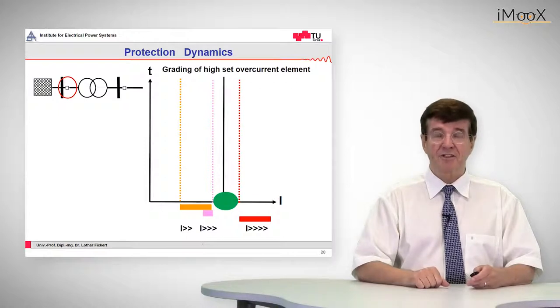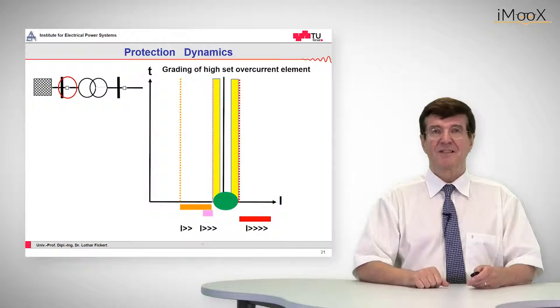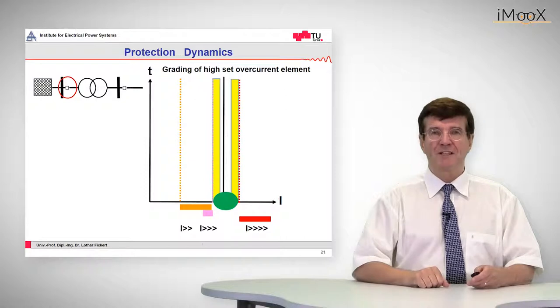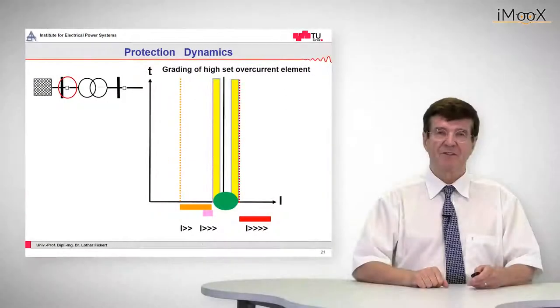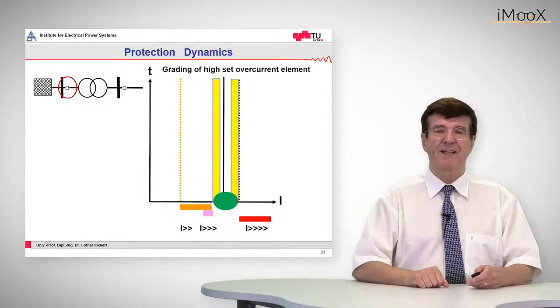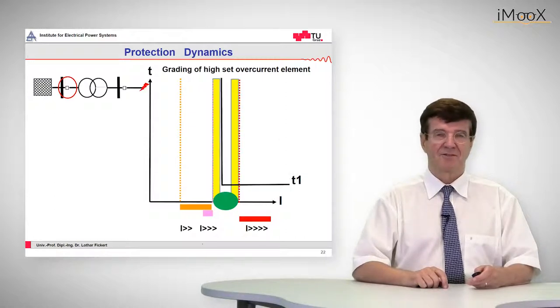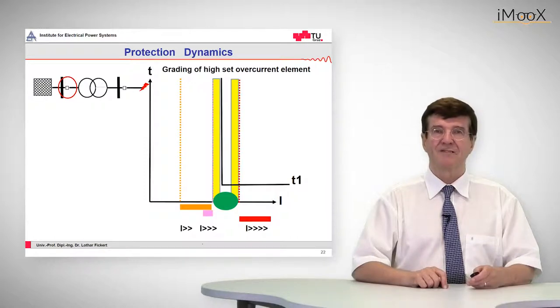In any case, the pickup value must not infringe with the safety margins. On the high set side, it must always pick up for a fault current, so the pickup value must be below that. On the other hand, it must not infringe with any fault on the low voltage side, so it must be above the highest low voltage side current. The tripping time is T1, because we must not wait for anything — tripping can be carried out immediately once such a fault has been detected upstream of the transformer.